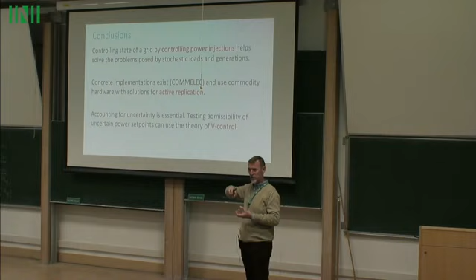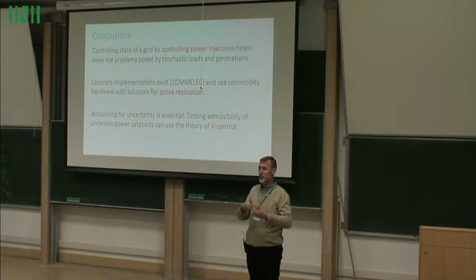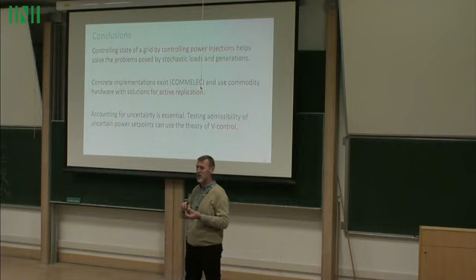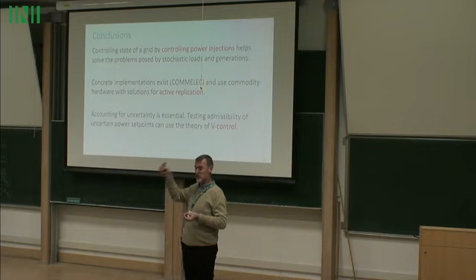If you need more, you need a higher level grid agent. This is a typical problem for the medium voltage grid agent, not on our campus because the grid is very stiff and we have no voltage problem, but on other grids we have this issue, where the grid agent of the medium voltage grid computes the optimal reactive power needed and instructs the local grids to provide it. All those grids are inverter-based, so they can provide whatever reactive power you want practically for free, so they do it too.